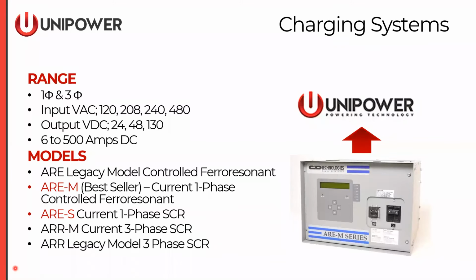Our charging systems, we have quite a few families of battery chargers that we offer. They can have single or three-phase input, a wide range of AC inputs, DC outputs of 24, 48, or 130 volts, and they range in output current from 6 to 500 amps. Now we make quite a few different models, from the ARE to the ARR legacy, but the two models we're talking about today are highlighted here in red, the ARE-M and the ARE-S. ARE-M is by far our biggest seller. The ARE-S is right behind that, but we still do offer those other legacy models.